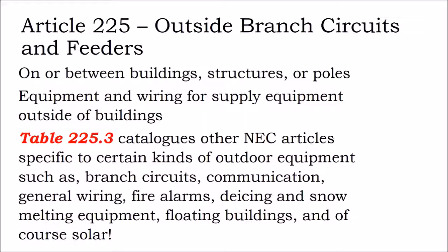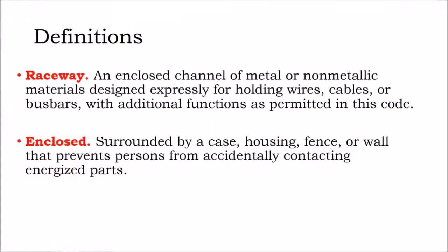You want to design a floating solar array. Well, there's a section of National Electric Code out there that governs floating buildings. So a new definition: raceway, an enclosed channel of metal or non-metallic materials designed expressly for holding wires, cables, or bus bars with additional functions as permitted in this code.